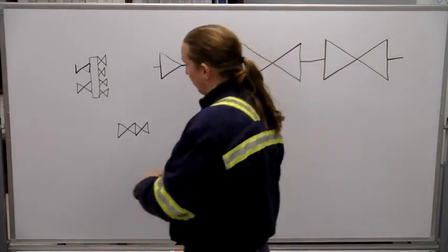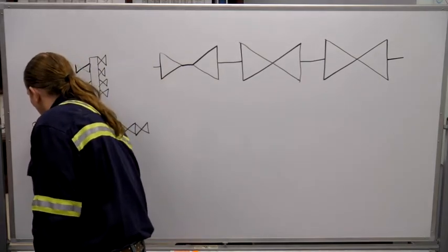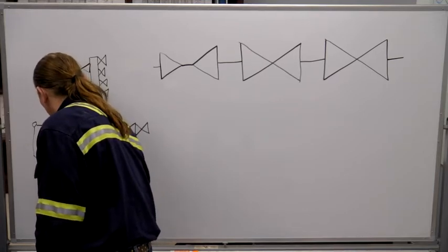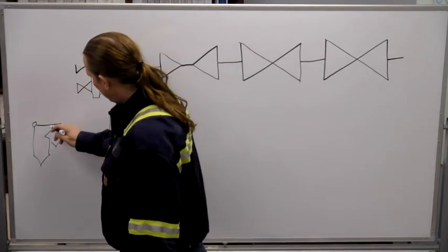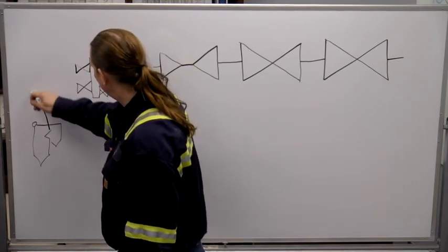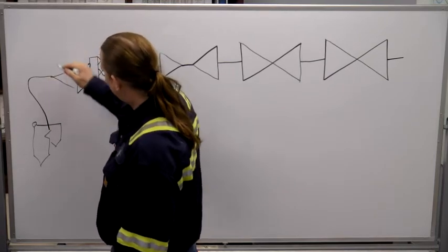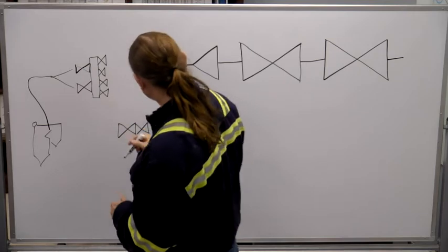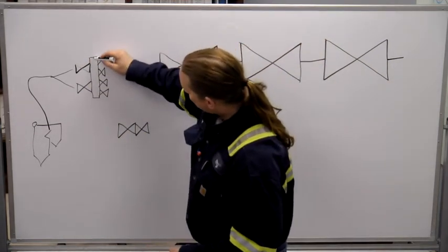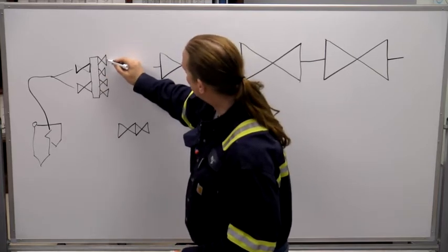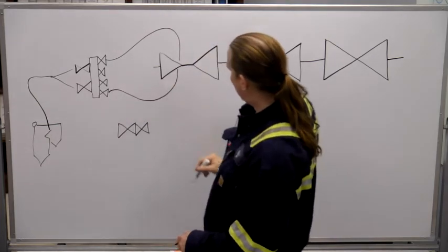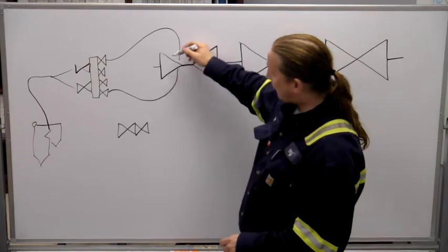So I'm going to draw the boiler over here. You've got a boiler, and coming out of the boiler it's a main steam header. You've got 2,500 pounds of steam and they go through two main steam stop valves, and then that goes to a common steam chest, that goes to four control valves, and then they go into the turbine — the high pressure part of the turbine.